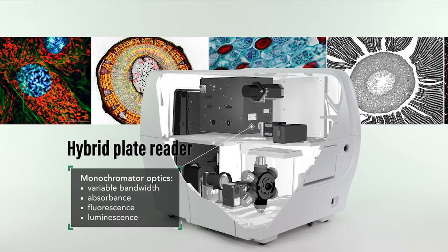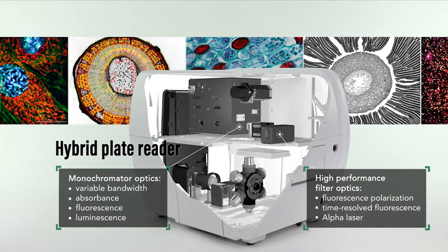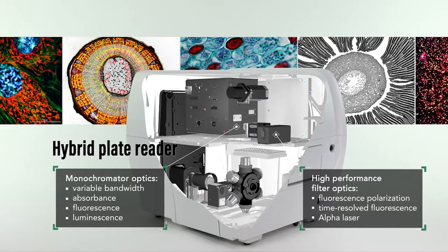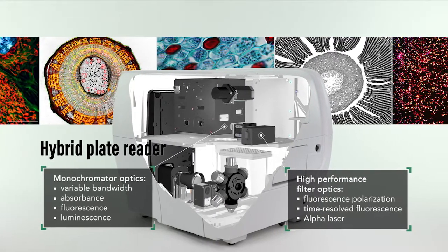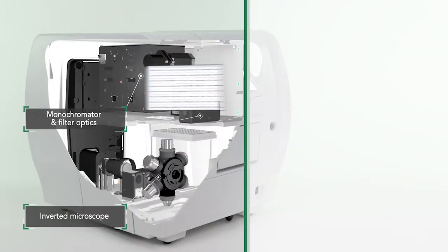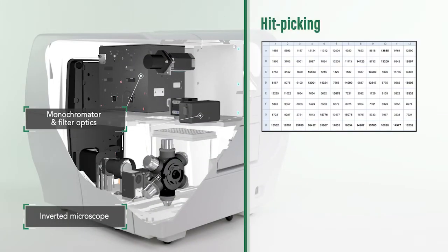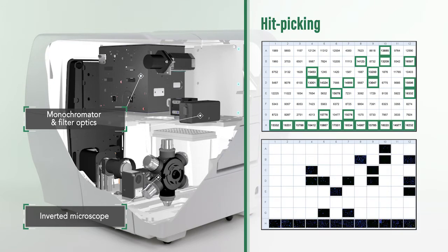With its patented combination of imaging and multimode detection, Citation is an advanced plate reader that delivers both the flexibility and performance you need for any microplate assay in your lab. Multi-mode detection used in conjunction with imaging provides effective hit-picking for increased efficiency and throughput. As an example, Gen5 quickly identifies green fluorescent protein-positive wells. Only those wells are imaged, saving time and computer hard drive space.